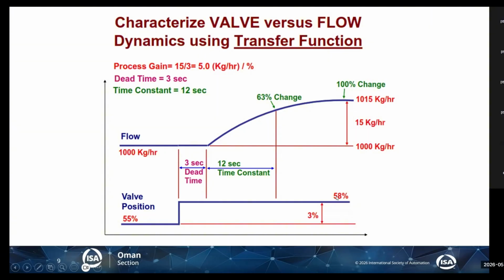So you can see our current MV value is 58. The previous one is 55, so the difference is 3. Our current flow is 1015, the previous one is 1000, so the difference is 15. So process gain is 15 by 3, which is 5 kg per hour. So why is this important? By this process gain value, I can understand that a 1% opening in the valve will give me an effect of 5 kg in the flow. And this is something very important for all process control engineers, technicians, and control system guys.